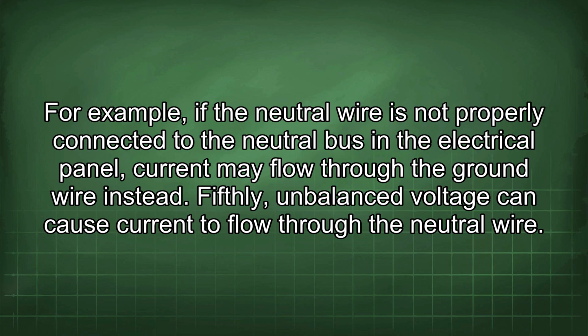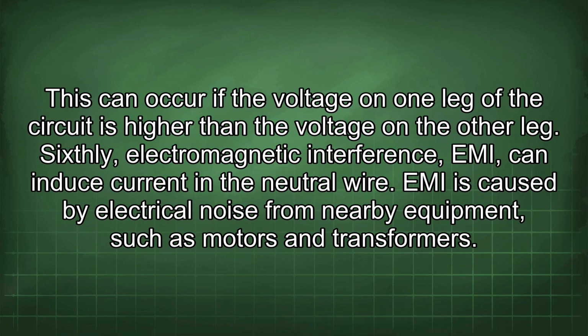Fifthly, unbalanced voltage can cause current to flow through the neutral wire. This can occur if the voltage on one leg of the circuit is higher than the voltage on the other leg. Sixthly, electromagnetic interference (EMI) can induce current in the neutral wire. EMI is caused by electrical noise from nearby equipment, such as motors and transformers.